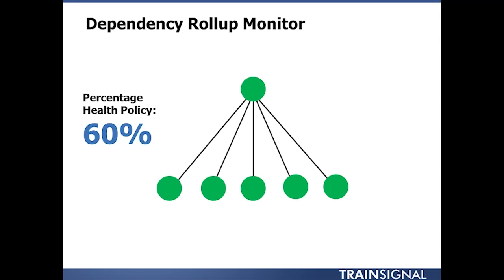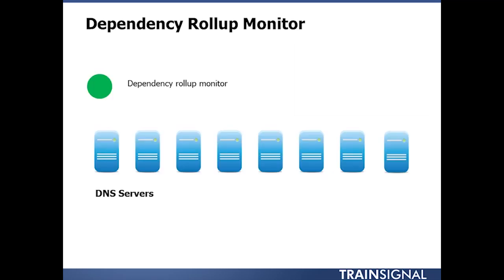This would mean that 60 percent of the monitored items would need to stay operational before the monitor goes red. In this example, the monitor would stay green even if two of the five items failed, but once that third item failed, the 60 percent availability threshold would be violated and the monitor would go red.